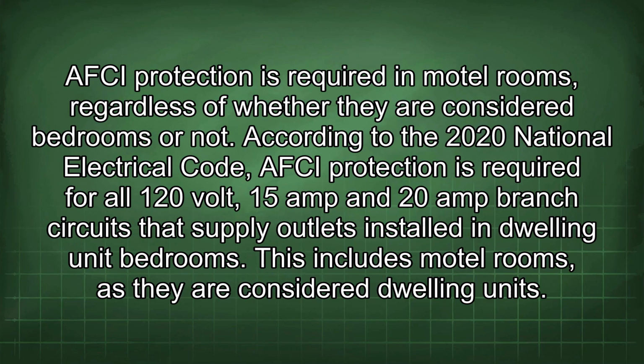AFCI protection is required in motel rooms, regardless of whether they are considered bedrooms or not. According to the 2020 National Electrical Code, AFCI protection is required for all 120-volt, 15-amp and 20-amp branch circuits that supply outlets installed in dwelling unit bedrooms. This includes motel rooms, as they are considered dwelling units.